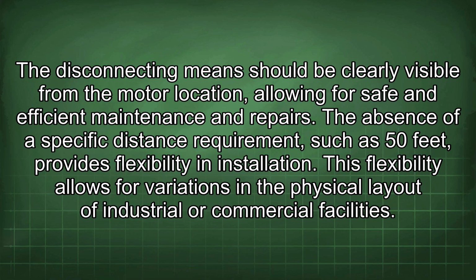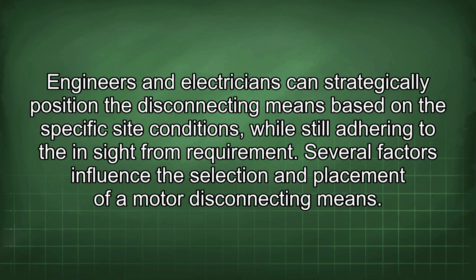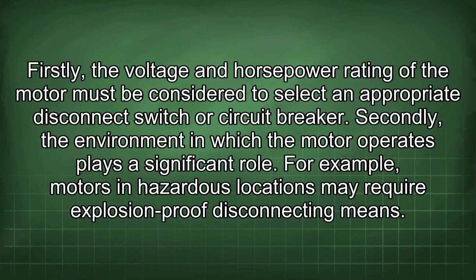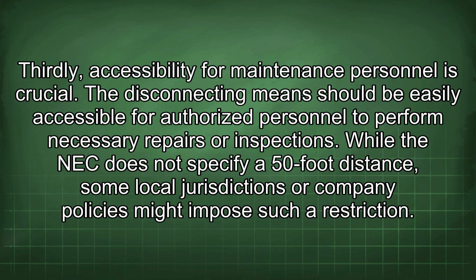The absence of a specific distance requirement, such as 50 feet, provides flexibility in installation. This flexibility allows for variations in the physical layout of industrial or commercial facilities. Engineers and electricians can strategically position the disconnecting means based on the specific site conditions while still adhering to the in-sight requirement. Several factors influence the selection and placement of a motor disconnecting means. Firstly, the voltage and horsepower rating of the motor must be considered to select an appropriate disconnect switch or circuit breaker. Secondly, the environment in which the motor operates plays a significant role. For example, motors in hazardous locations may require explosion-proof disconnecting means. Thirdly, accessibility for maintenance personnel is crucial. The disconnecting means should be easily accessible for authorized personnel to perform necessary repairs or inspections.